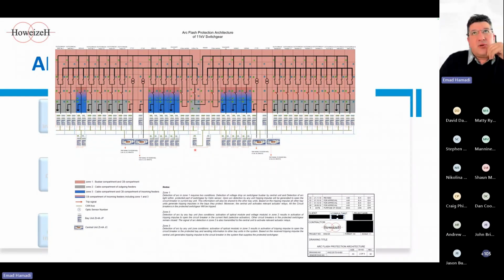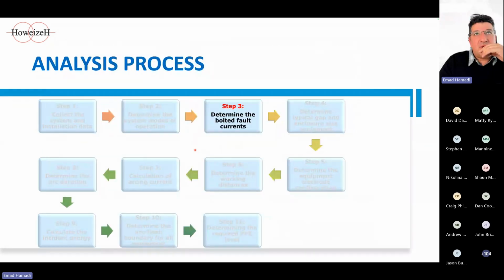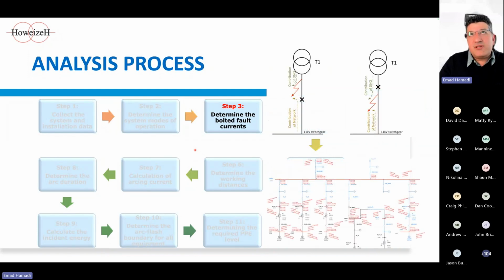So, back to our colleague's question regarding the protection settings. Sometimes you cannot reduce that because you make something else worse. So a protection study and arc flash relays are two of the main measures you can use to end up with a low incident energy throughout your network. The next step is to determine the fault current. It's very important to run a thorough short circuit study, and if one is not available, it will be necessary to perform one as part of the arc flash study.